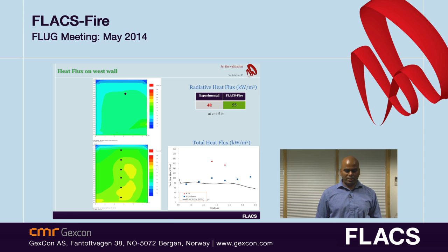The heat flux on the west wall, similarly the radiative heat flux and total heat flux on the west wall, is also shown here. For the total heat flux and the radiative heat flux, the agreement between the FLACS-Fire and the experiment data is very nice.